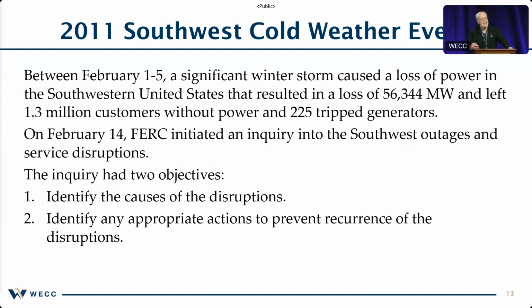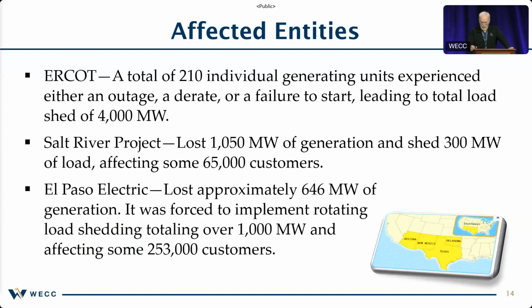Now, one of the characteristics of this event is that it's the first cold weather inquiry that FERC actually participated in. And when they participated, they had a couple of different goals. They wanted to identify the causes of the disruptions. So what's causing these cold weather problems that we're having? And they wanted to look at appropriate actions to prevent reoccurrence. So how do we fix it? When we look at the 2011 event, we can see that not only did it impact ERCOT, which is Texas, but it also impacted a couple of entities within the Western Interconnection. When we look at that impact, ERCOT lost 210 individual generating units. They were an outage, a derate or fail to start, as we saw in our comparison. And they shed 4,000 megawatts of load.